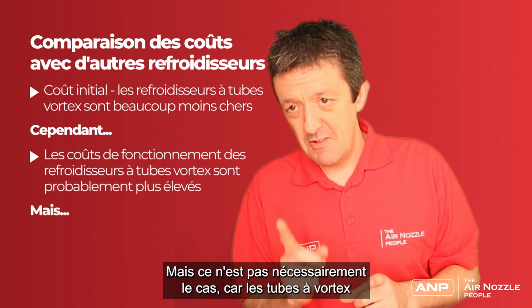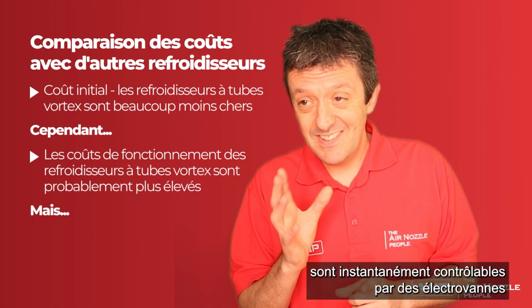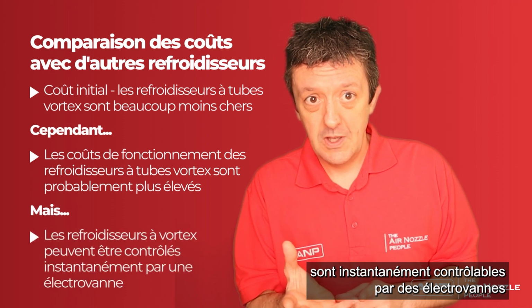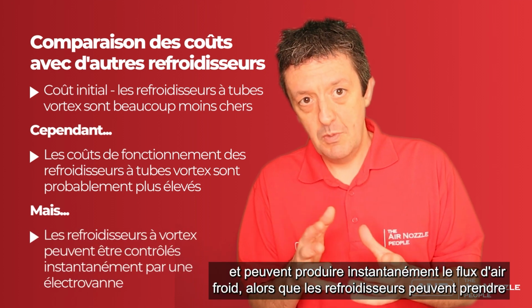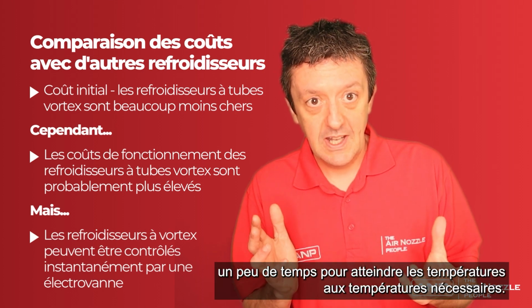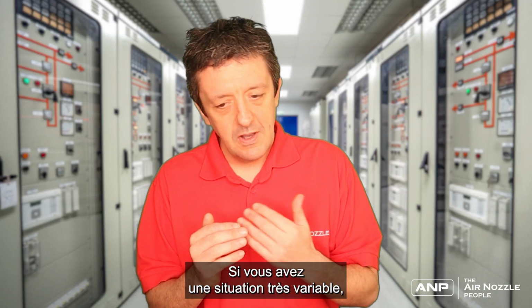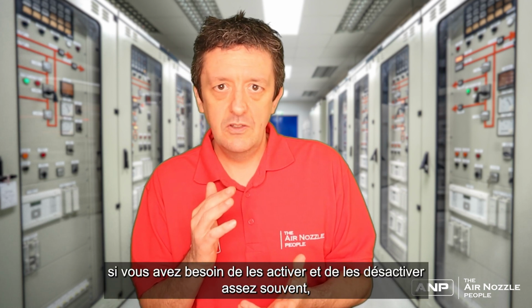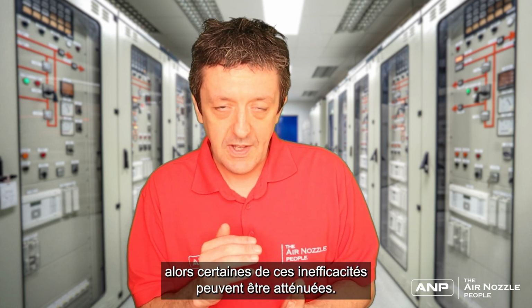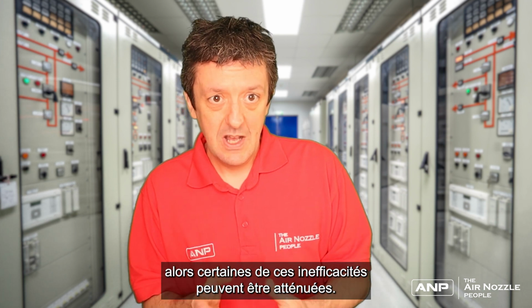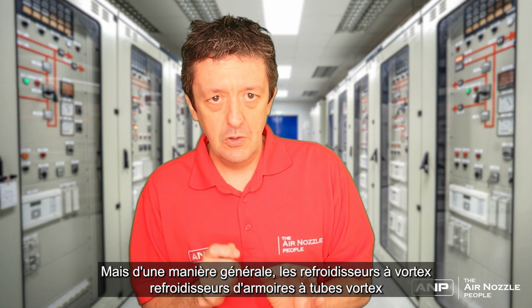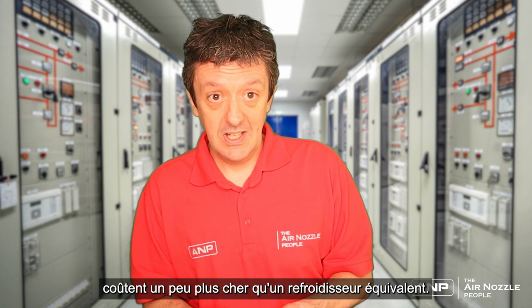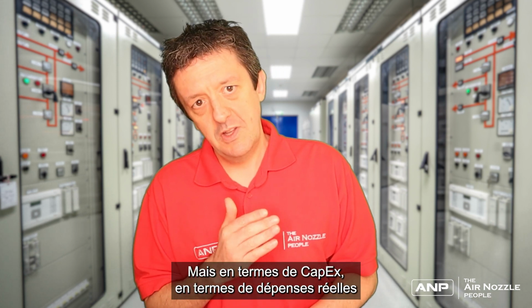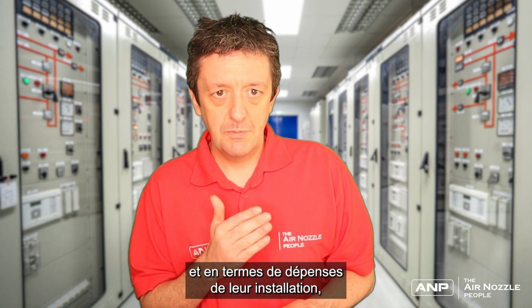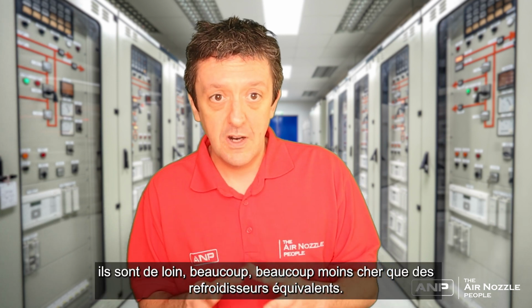But this is not necessarily the case, as Vortex Tubes are instantly controllable by solenoid valves and can instantly produce their cold air stream, whereas chillers can take a little bit of time to actually get down to the temperatures that they need to. If you're having a very variable situation, if you need to have them on and off quite a lot, then some of those inefficiencies can be mitigated. But generally speaking, a Vortex Tube cabinet cooler will cost a little bit more to run than an equivalent chiller. But in terms of capex, in terms of the actual expenditure, and in terms of the expense of actually getting them installed, they are far cheaper than equivalent chillers.